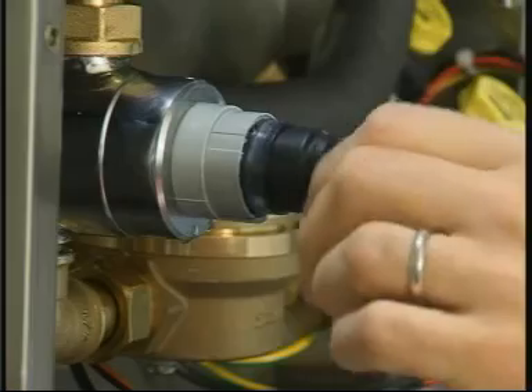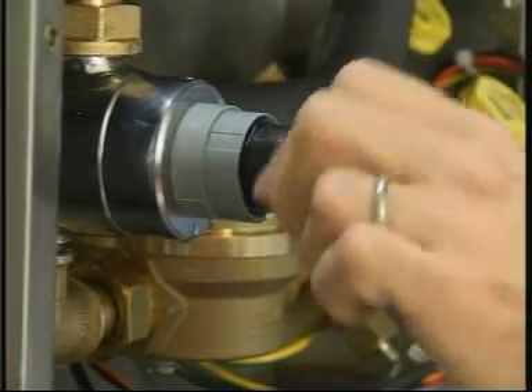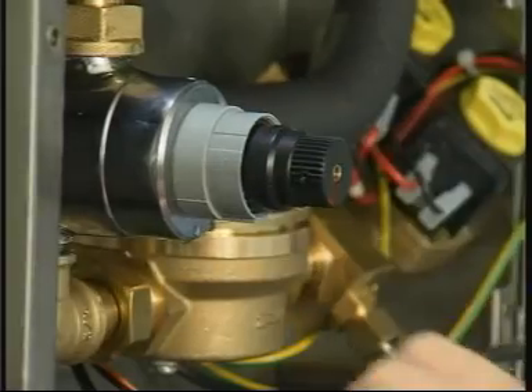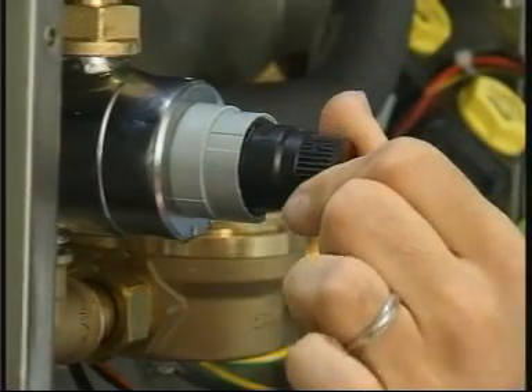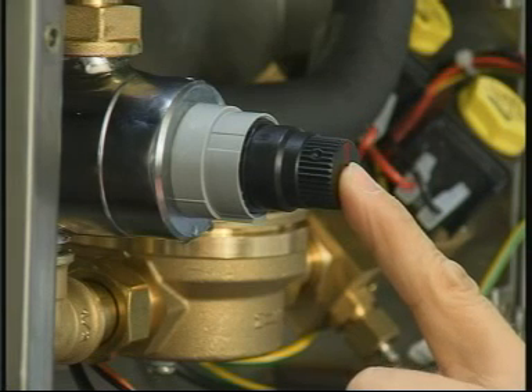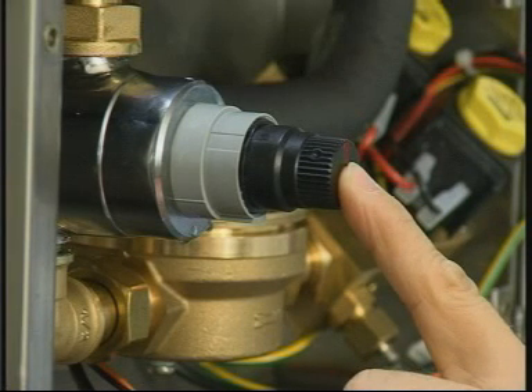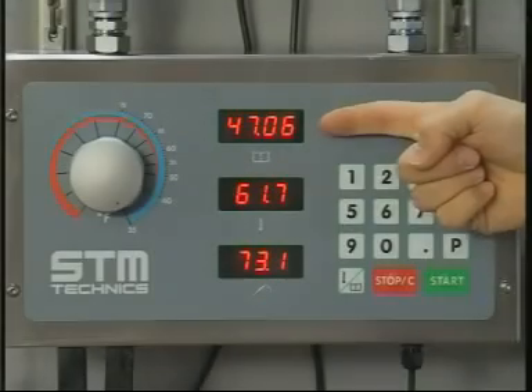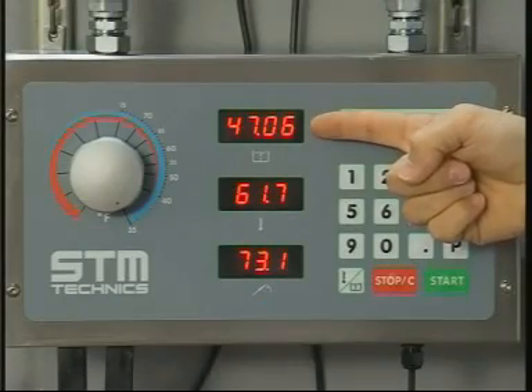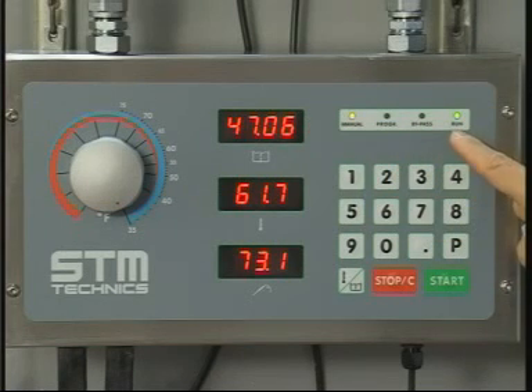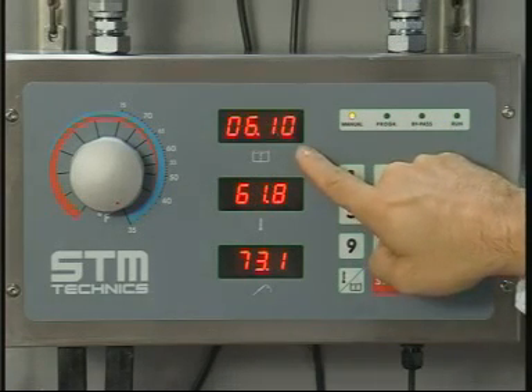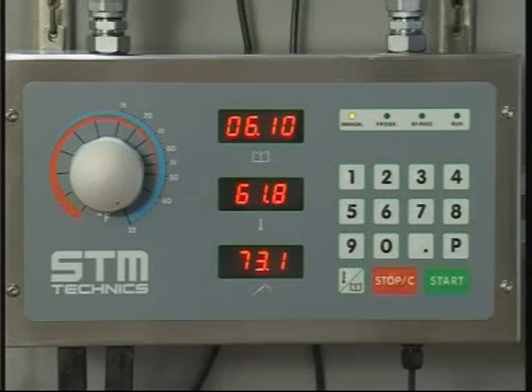Open the two inlet ball gate valves and press the start key. With the red sign on the knob pin in the 12 o'clock position, the temperature at delivery must be 32.5 degrees centigrade or 90 degrees Fahrenheit. Litre counter error. During the delivery, the countdown on the upper display stops, even with the run LED being lighted, and after some seconds, the machine goes into alarm and the writing R.L appears on the display.